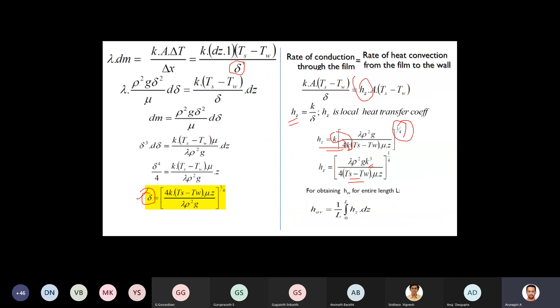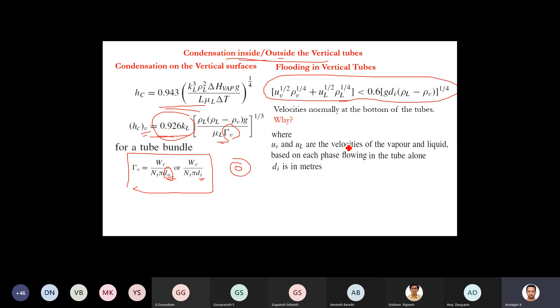Okay. So if the condensation takes place on only one side, you can use this equation based on the orientation: horizontal shell side or horizontal tube side, vertical shell side or vertical tube side. Vertical means you have to check this condition, flooding. You might have studied in mass transfer what flooding is, because what will happen if the condensate loading is more, then it will be stored in the pipe. In such a case, it is partially occupied by vapor and partially occupied by the condensate.